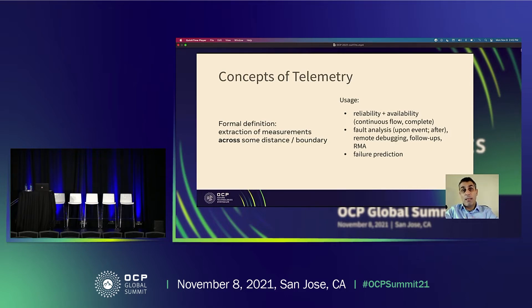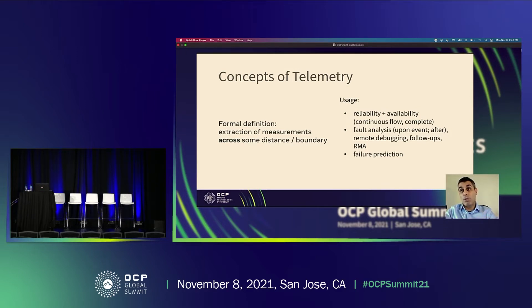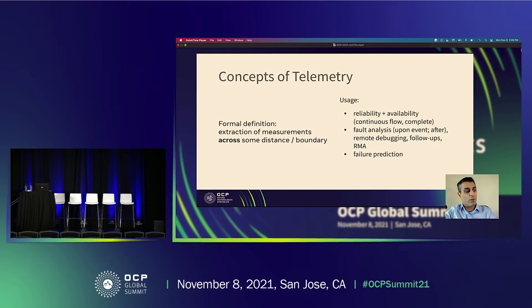We use telemetry to be able to analyze faults — first of all, to track if the faults have occurred at all, and then be able to debug them, drill them down into the root cause, do some follow-ups, understand which conditions have contributed to the fault, and then as we may want to send some hardware back for RMA, to be able to explain to the vendors what kind of faults have led us to that decision.